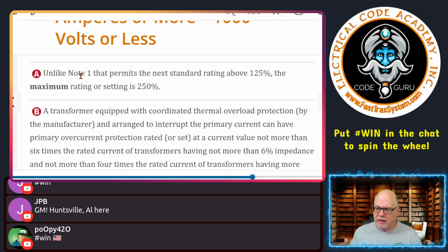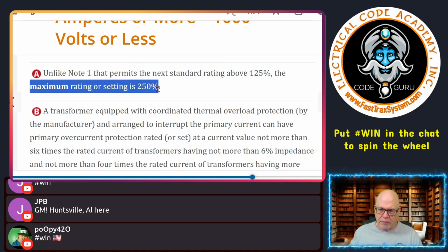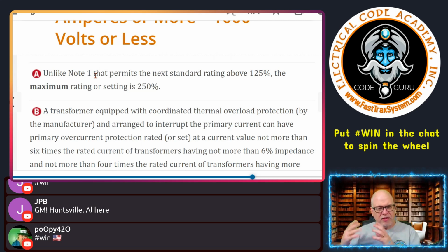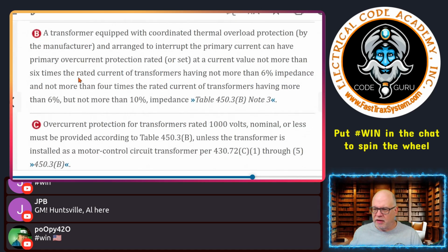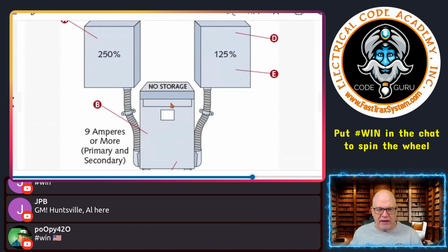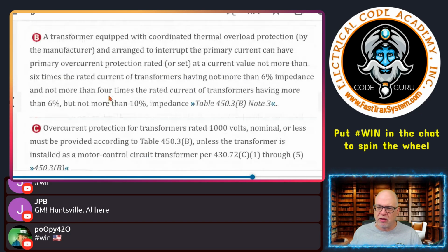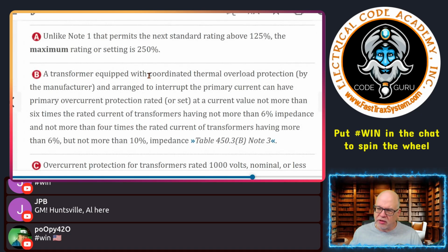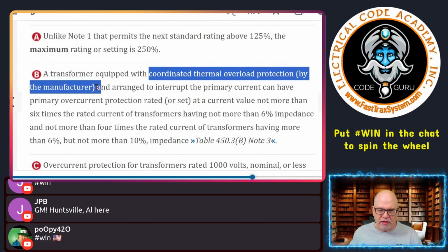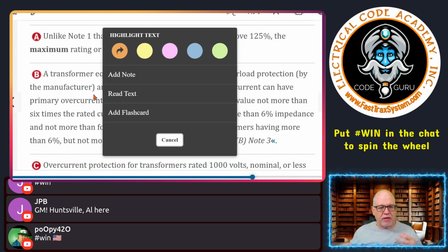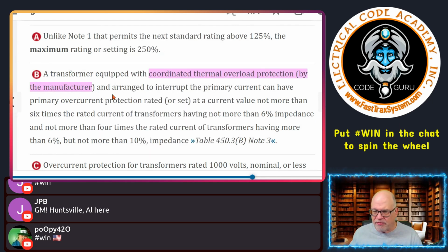So unlike note 1, that permits the next standard rating above 125%, again, here you notice that the maximum rating or setting is 250%. So that's what it said in the code, and that's what it says in the table over on 450.3(B). Okay, so that's the first part. Refer to B, which is talking about the transformer right here. So the B callout is saying a transformer equipped with a coordinated thermal overload protection, again, by the manufacturer. It's basically supplied as part of the equipment, and you're going to pay for it. Trust me. It's not a gift from the manufacturer, right?